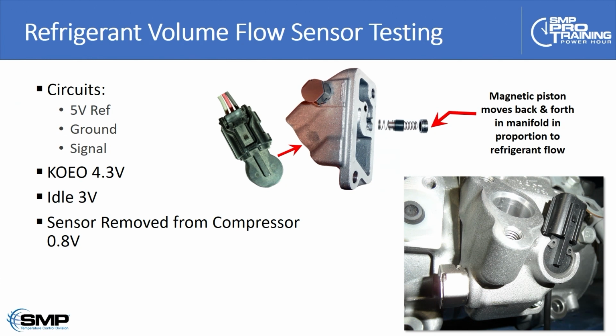And there's a bypass passage, a tiny passage running parallel to the discharge port. As refrigerant volume flow increases, you get a bigger pressure drop across the restriction, and the little magnet is pushed back and forth. It's the movement of that magnet that creates the voltage output change on the refrigerant volume flow sensor signal.